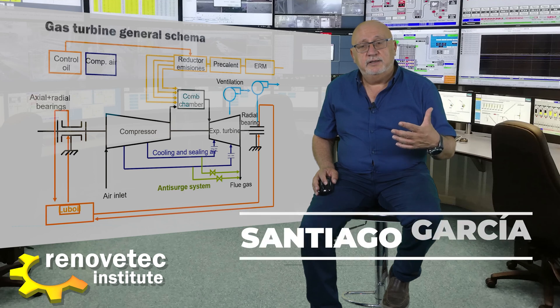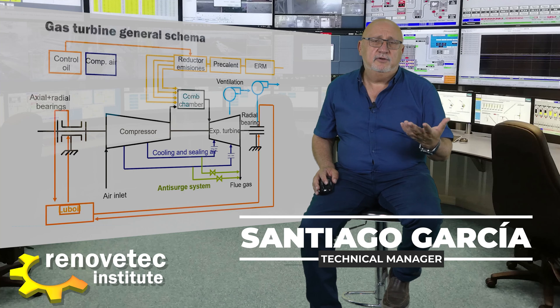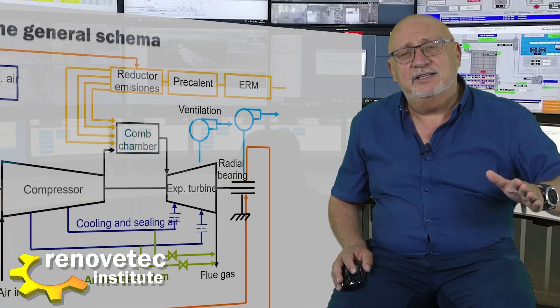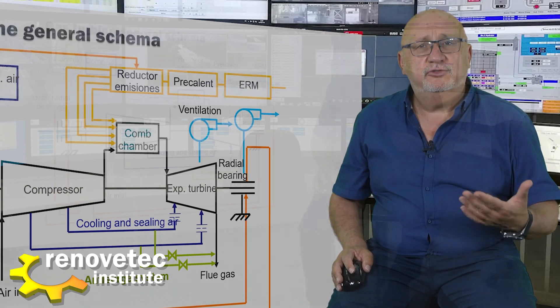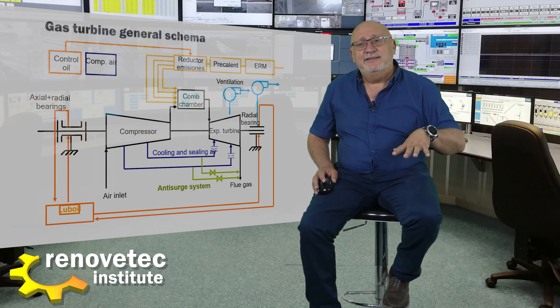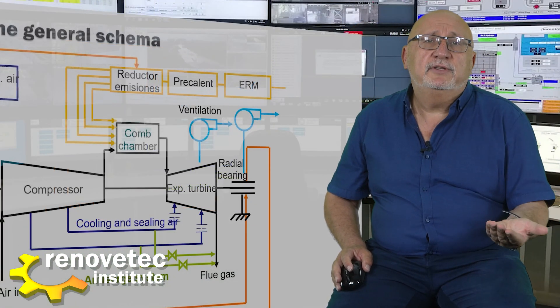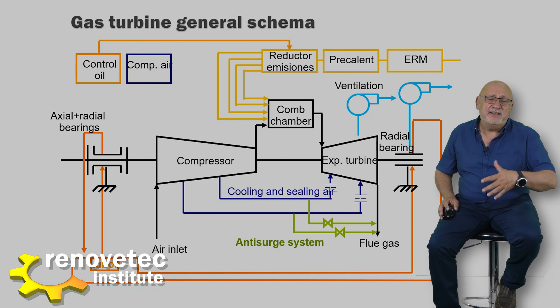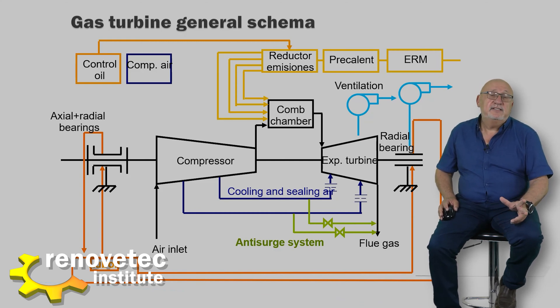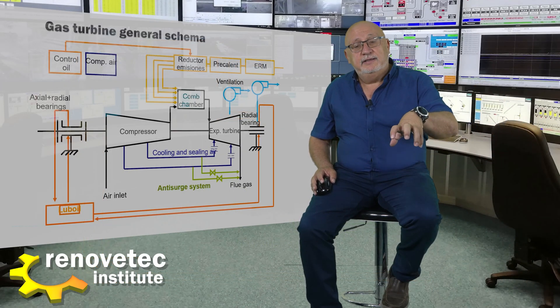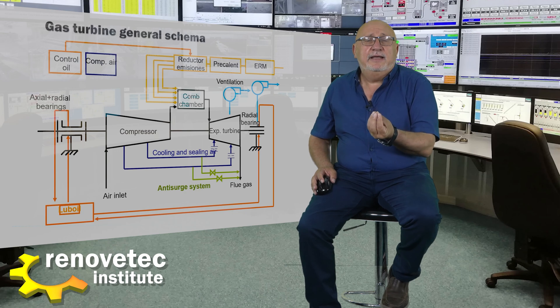The turbine generates very high noise levels near the unit. To prevent this noise from affecting people, the turbine is normally installed inside an enclosure. Inside this enclosure, a small amount of thermal energy is emitted by radiation from the turbine. The enclosure is well isolated to prevent noise from escaping, but the interior is heated by radiation emitted by the gas turbine, so it is necessary to cool the inner part of the enclosure by introducing and extracting air.